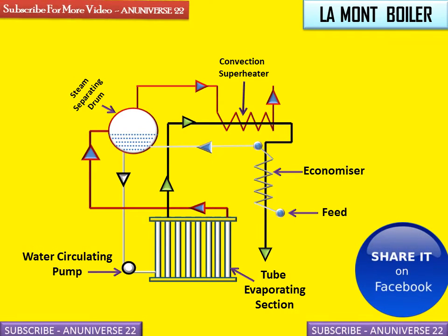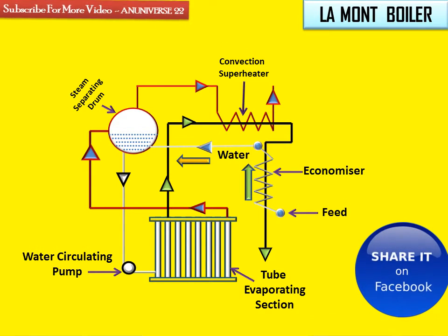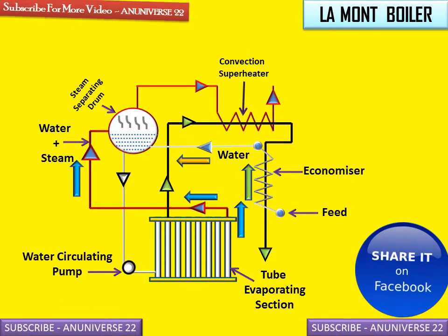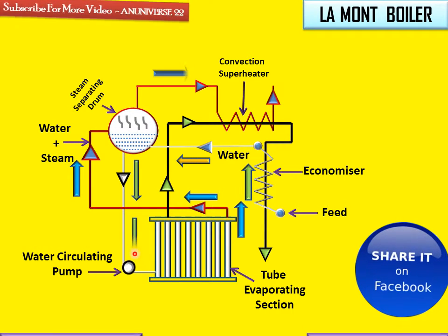A feed pump forces the water into the economizer, where the temperature of the water increases by getting heat from the flue gases. This water is then forced into the evaporator tube by the circulating pump. The water coming out from the steam separator is recirculated through the evaporator tube with the help of the centrifugal pump, producing a mixture of water plus steam that is sent back to the steam separator.